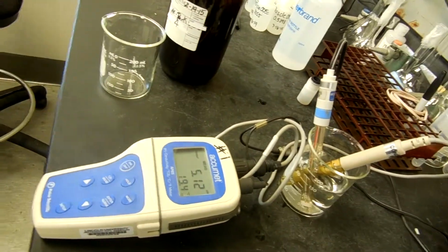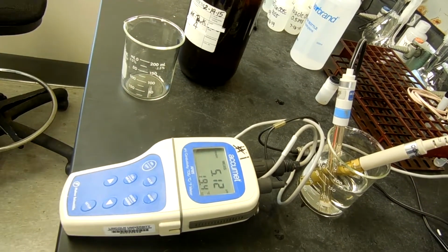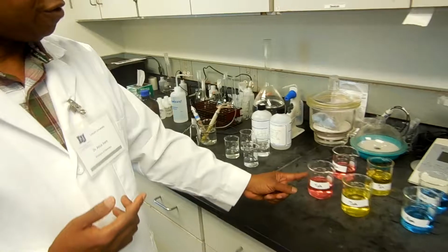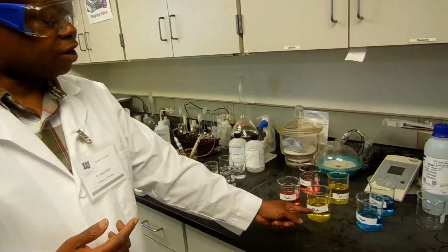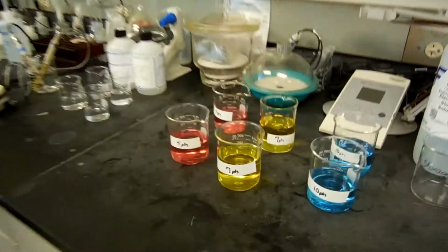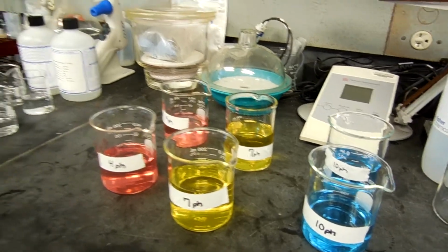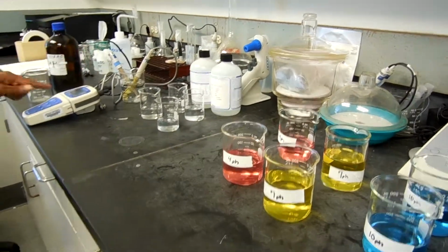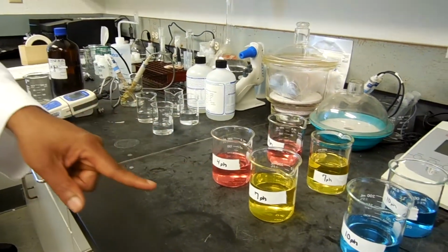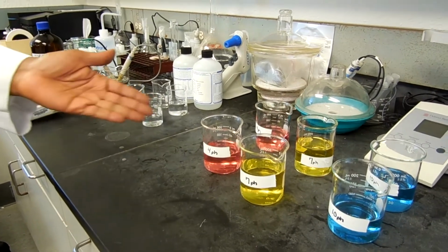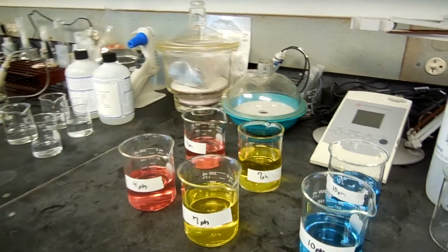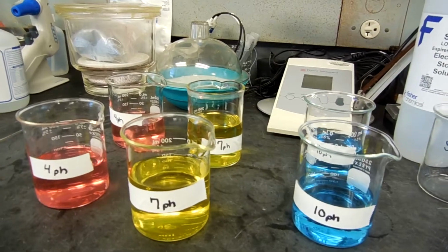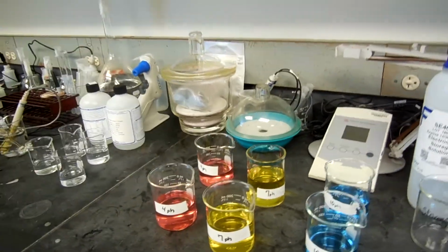Calibration means you have to feed the instrument with solutions. For pH, you have a set of buffer solutions at pH 4, pH 7, and pH 10. You feed the pH electrode to these solutions to calibrate the instrument to respond to them. Again, you have to be sure that the solutions are of integrity, meaning that they have not expired, and that you purchased them from a good source.